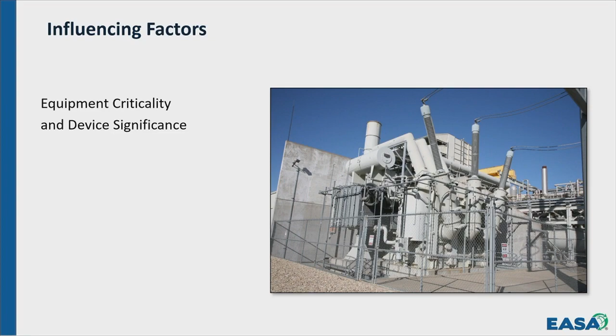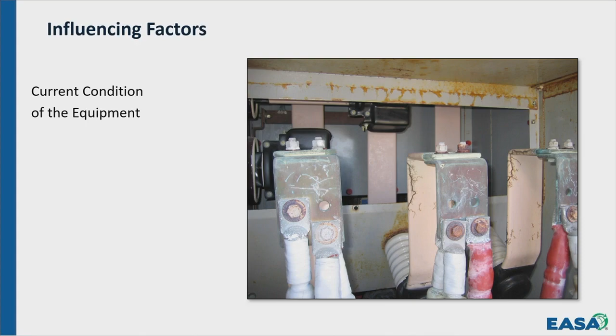Also, the current condition of the equipment matters. Is it old? Does it have tracking or treeing, like this bus bar feeding a motor? Sometimes you have a medium voltage machine that keeps tripping off, and they say it's the motor, but maybe it's not the motor - maybe the heaters in the cell aren't on, it hasn't been maintained, and you keep tripping at the leads of the motor in the junction box.